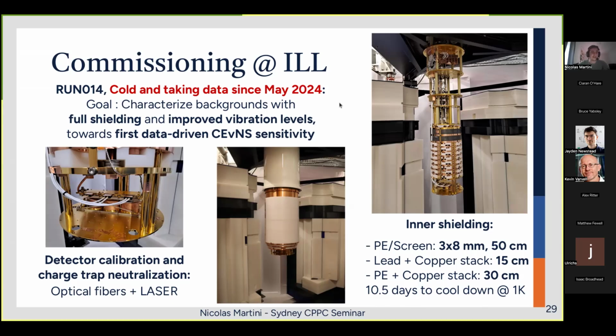There's another interesting thing that I can mention about this run of the Ricochet cryostat, and it's the test of a new idea in terms of detector calibration and charge trap neutralization. So in terms of detector calibration, as I mentioned before, we are using the 10.37 and 1.3 keV peaks from germanium-71 electron capture. But the activity of these peaks tends to go down with time, and at some point you might not be able to see them anymore. So if you still want to be able to calibrate your detectors, you might want to have another source of calibration. And one way to do it is to bring optical fibers to your detector and to shoot with a laser some very short pulses directly on your crystals to be able to calibrate your data.